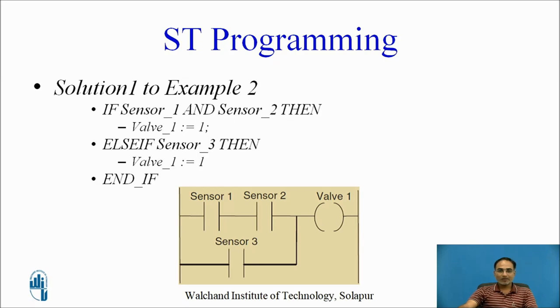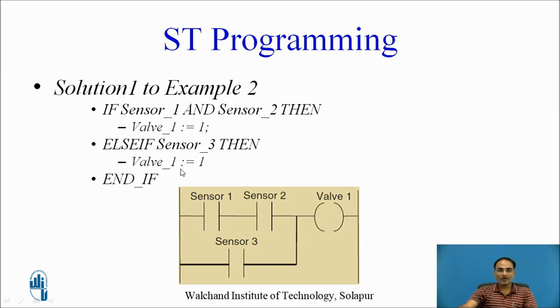The second solution using an IF-THEN block reads: IF Sensor1 AND Sensor2 THEN Valve1 := 1 ELSIF Sensor3 THEN Valve1 := 1 END_IF. The meaning is: if Sensor1 and Sensor2 outputs are both satisfactory then turn Valve1 on; else if Sensor3 output is satisfactory then also turn Valve1 on.